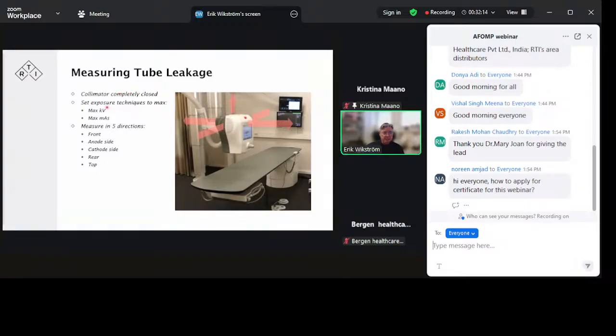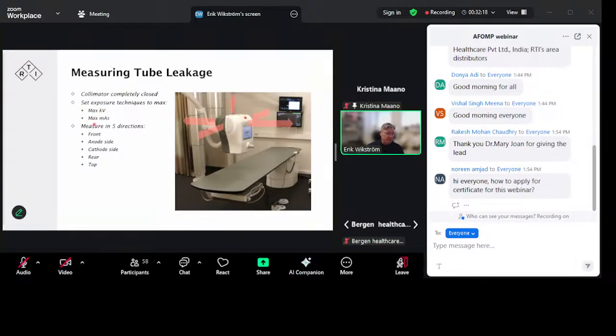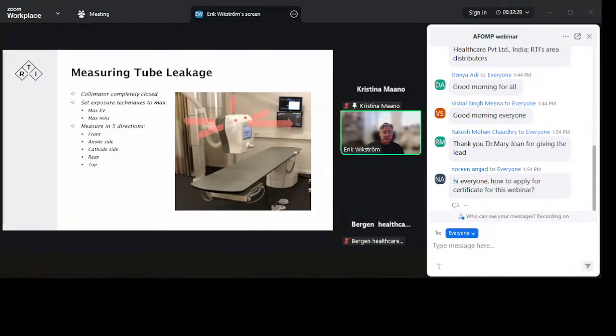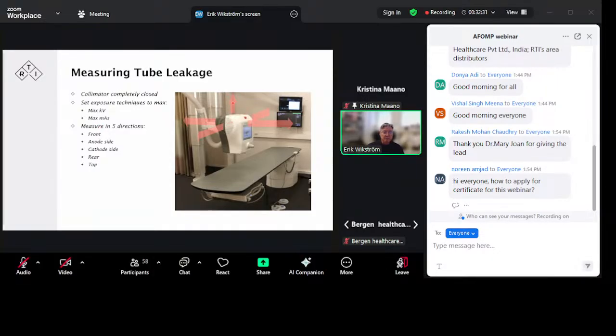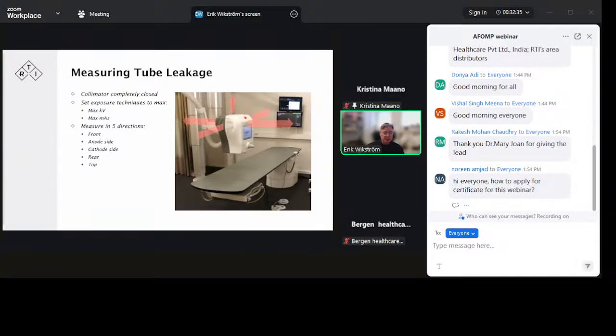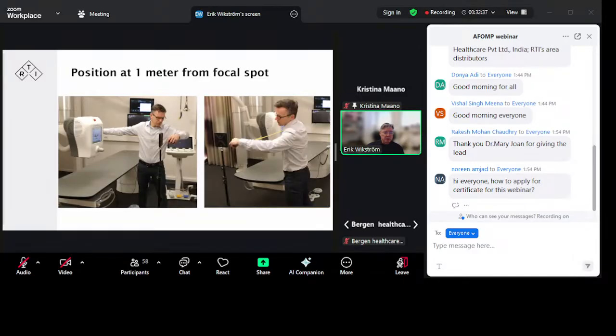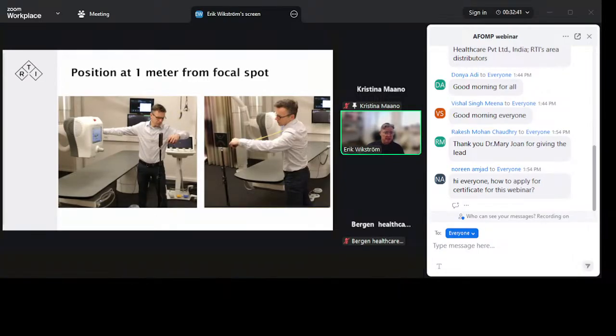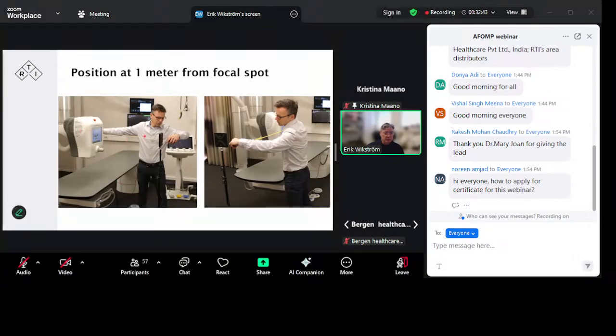Then setting the exposure techniques to maximum kV and maximum mAs, or what is recommended by the manufacturer. And then measuring in 5 directions: in the front, the anode side, the cathode side, rear, and the top. And sometimes that is a bit of a challenge. Could be an issue with space, finding enough space to the side to position the meter.